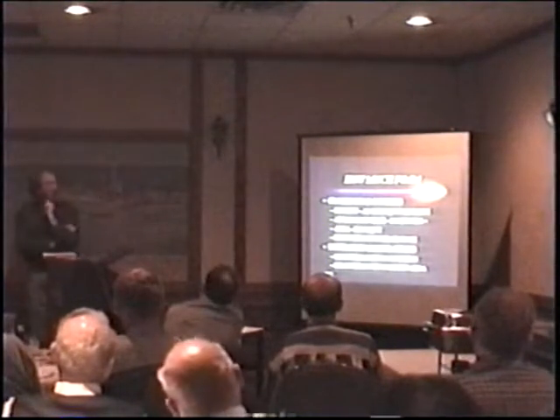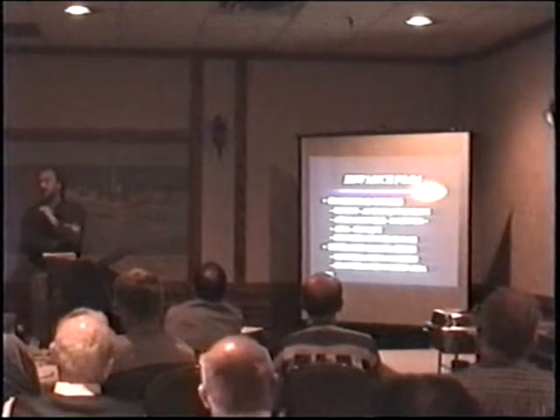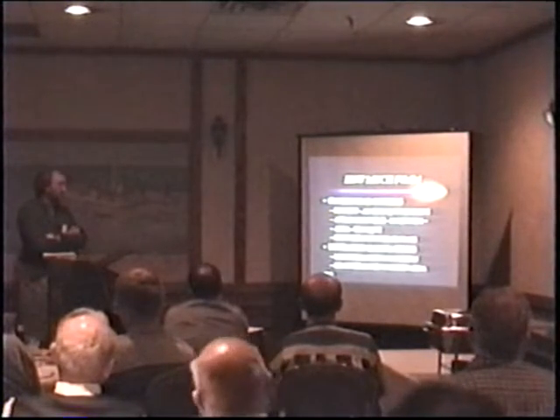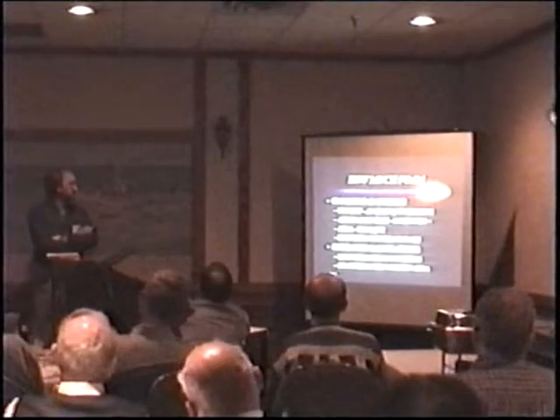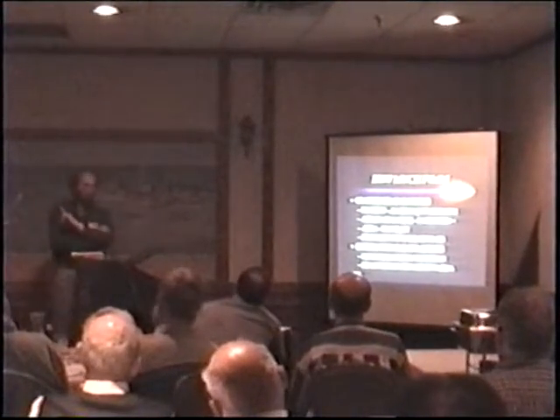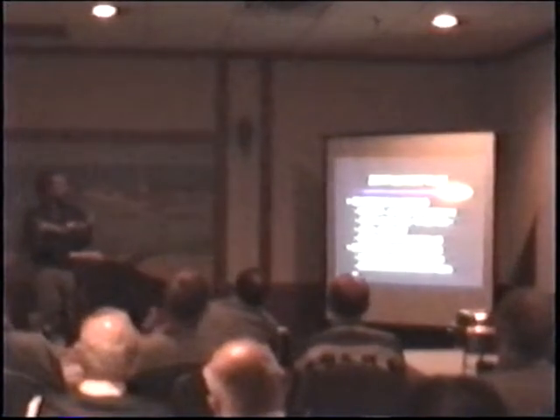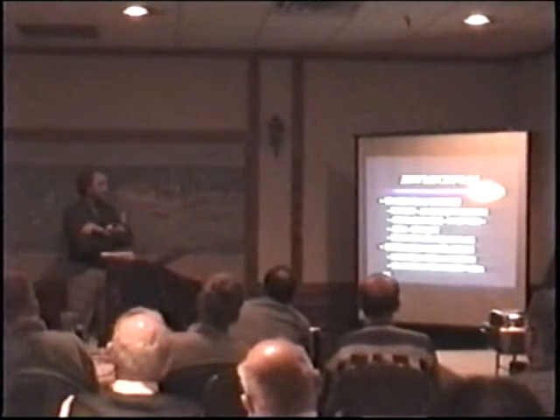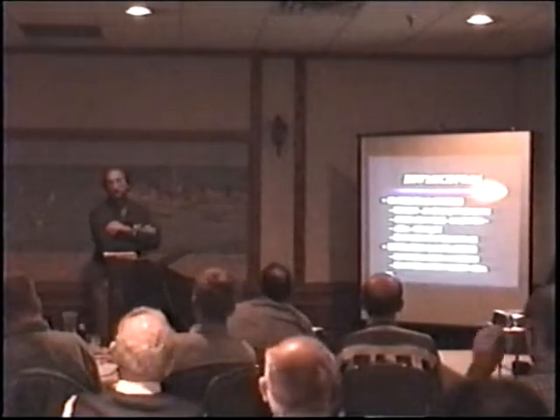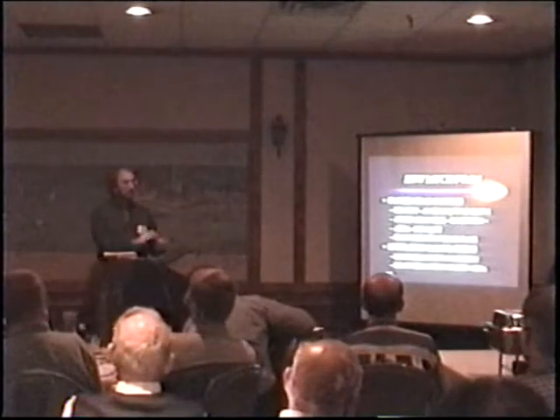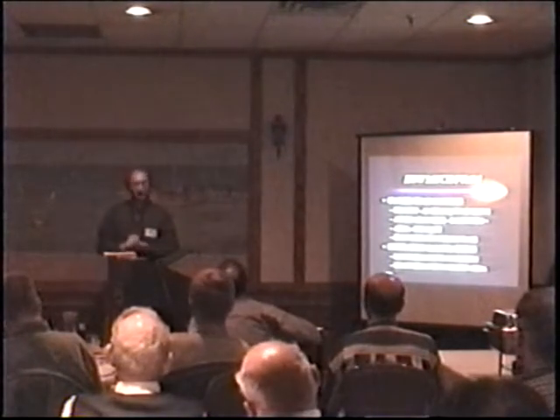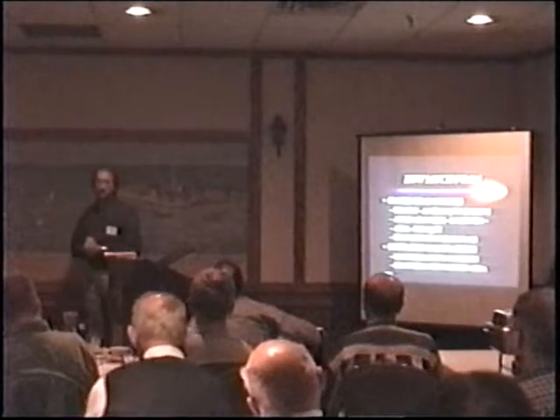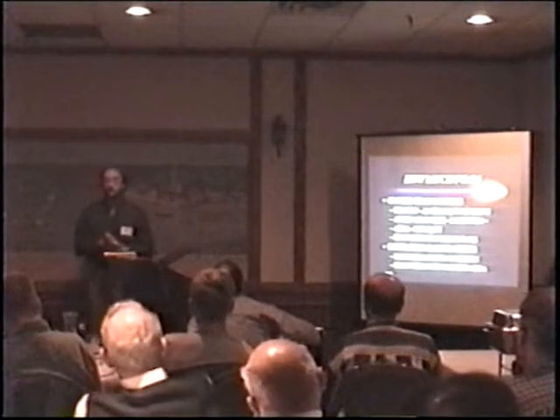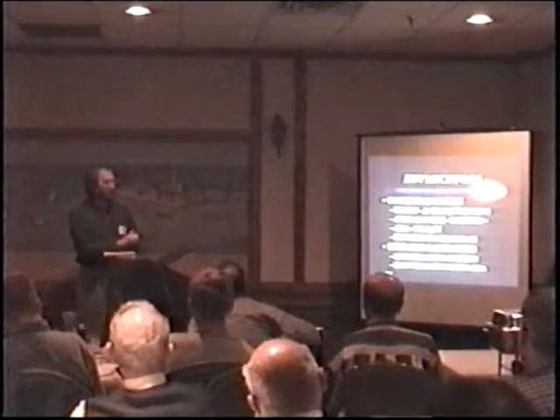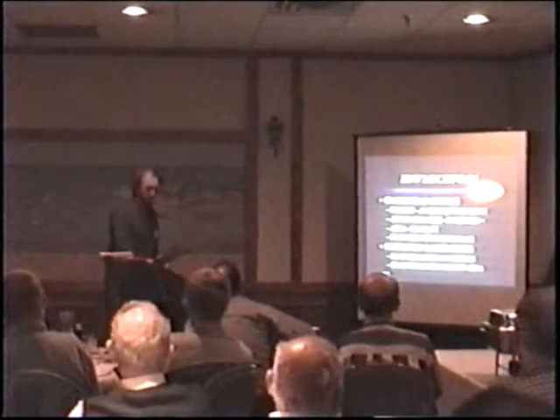Final sizing of your system is going to be based on your hydraulic calculations. And your hydraulic calculations for a closed head system demand two, if I recall. You have to calculate for your most demanding condition, and then you also have to run a calculation for your least demanding design area. Multiplying the area, the application, and the density, and the proportion percentage will get you in the ballpark for many purposes, but you've got to run your calc and see what you're actually going to use.